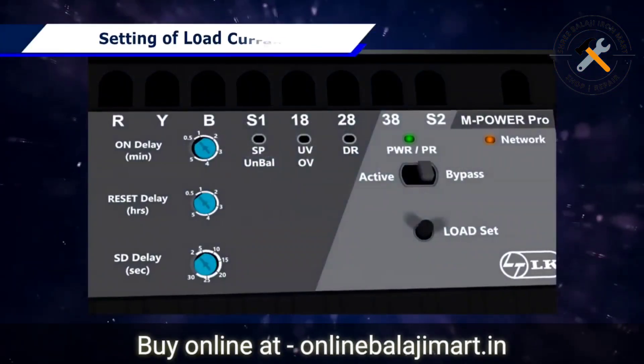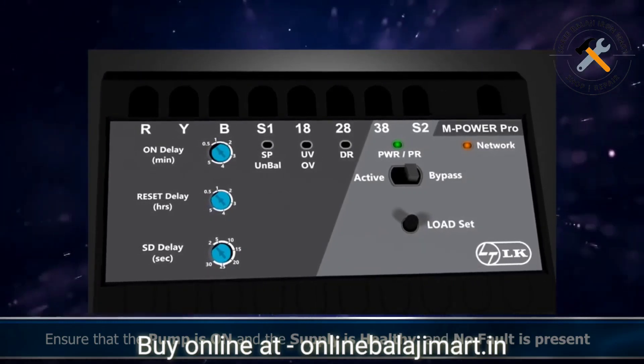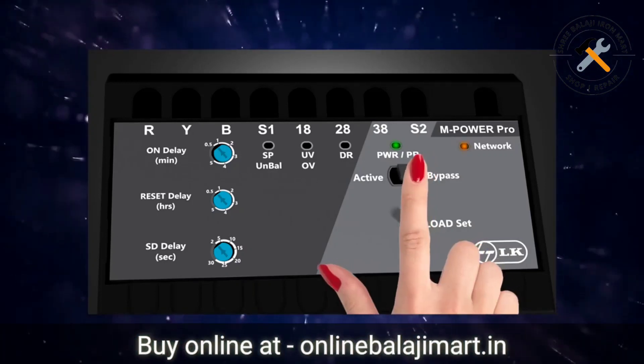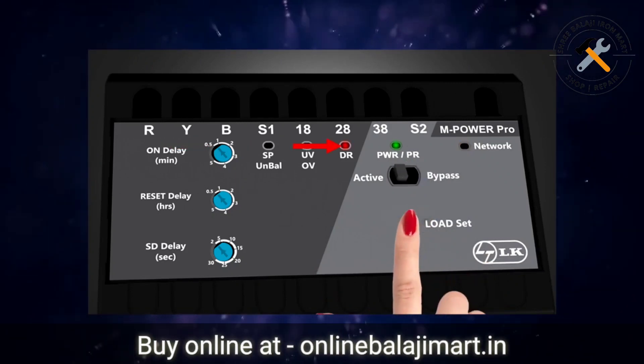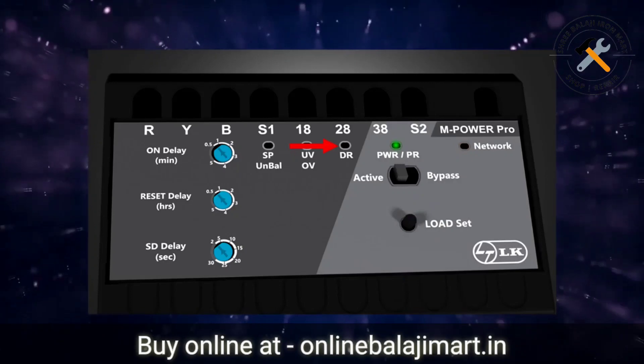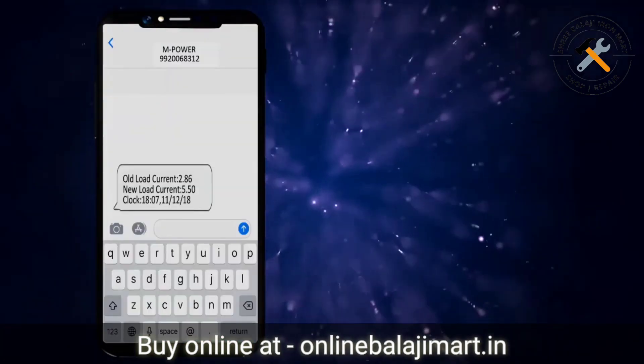Setting of load current. For setting load current, ensure that the pump is on, the supply is healthy, and no fault is present in the system. When all these conditions are met, move the mode selection slider switch to active mode and press the load set button. The DR LED will start blinking continuously. Keep the button pressed till this LED goes off, indicating that the load current has been set. You will receive an SMS confirming the set load current.